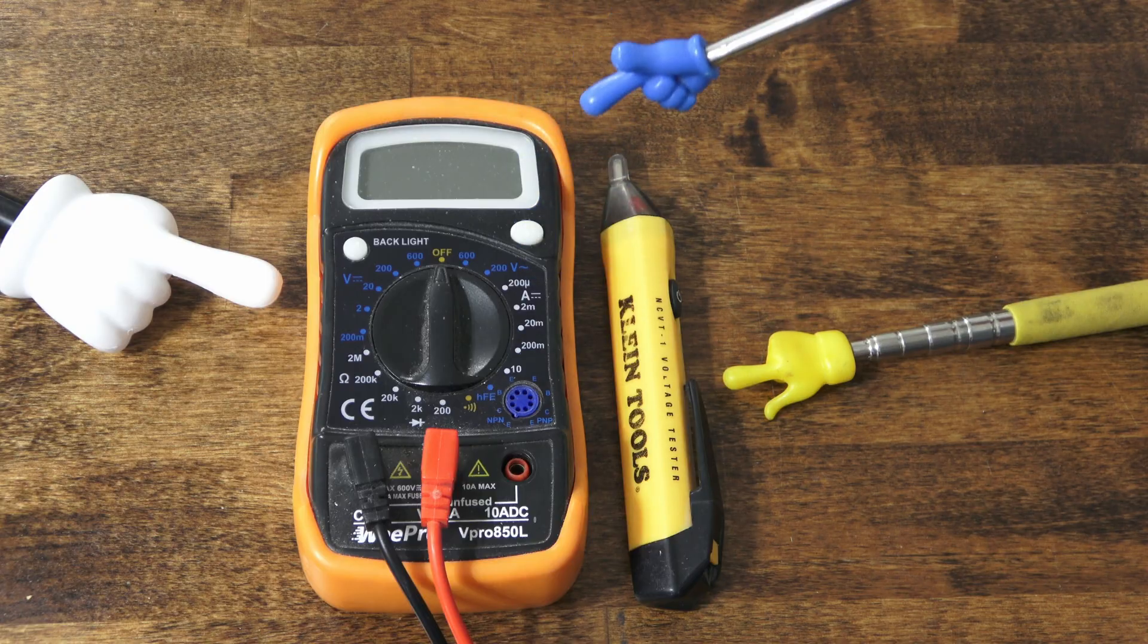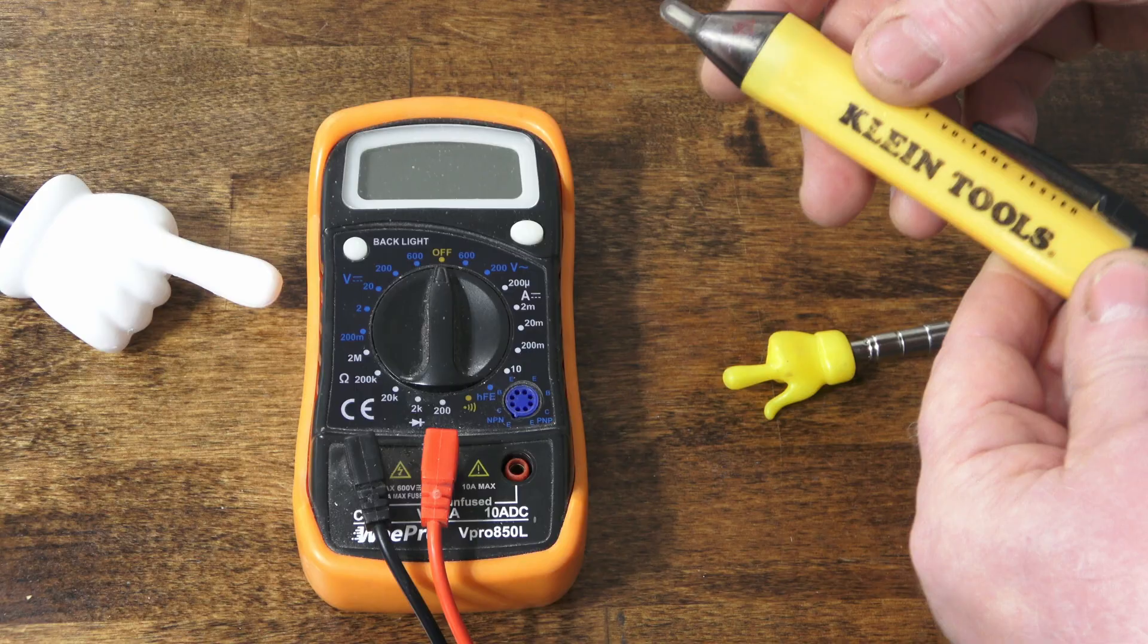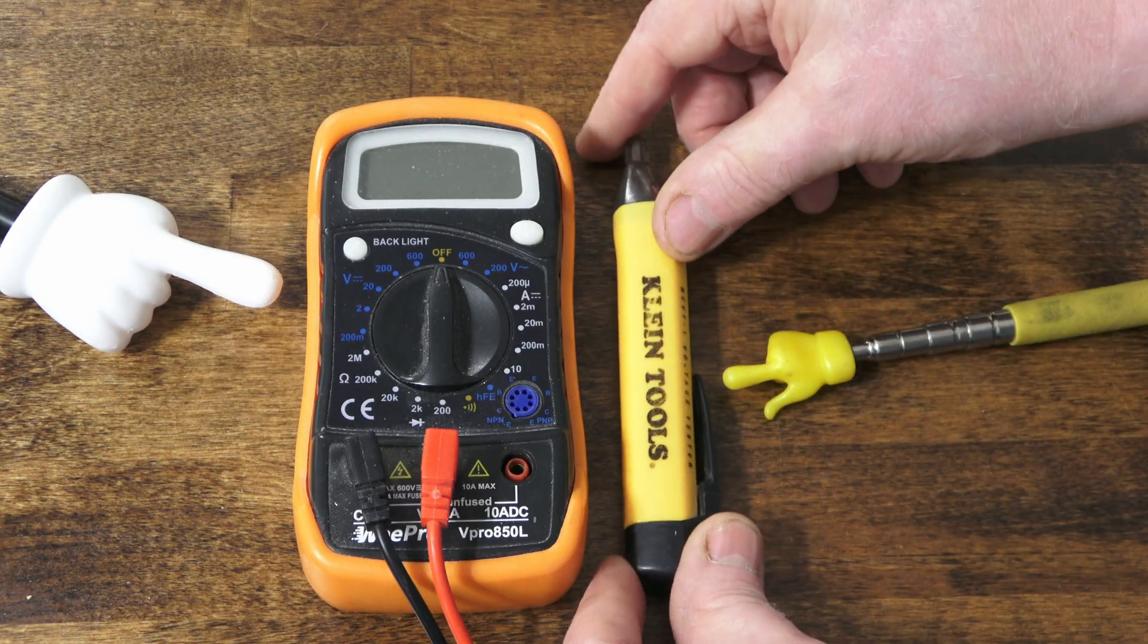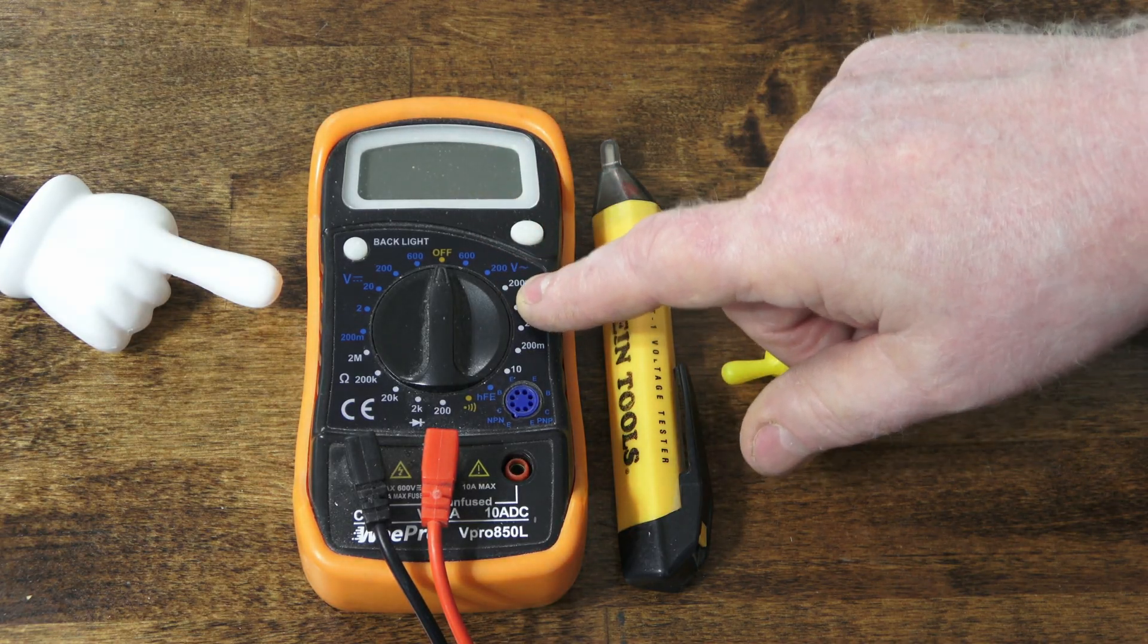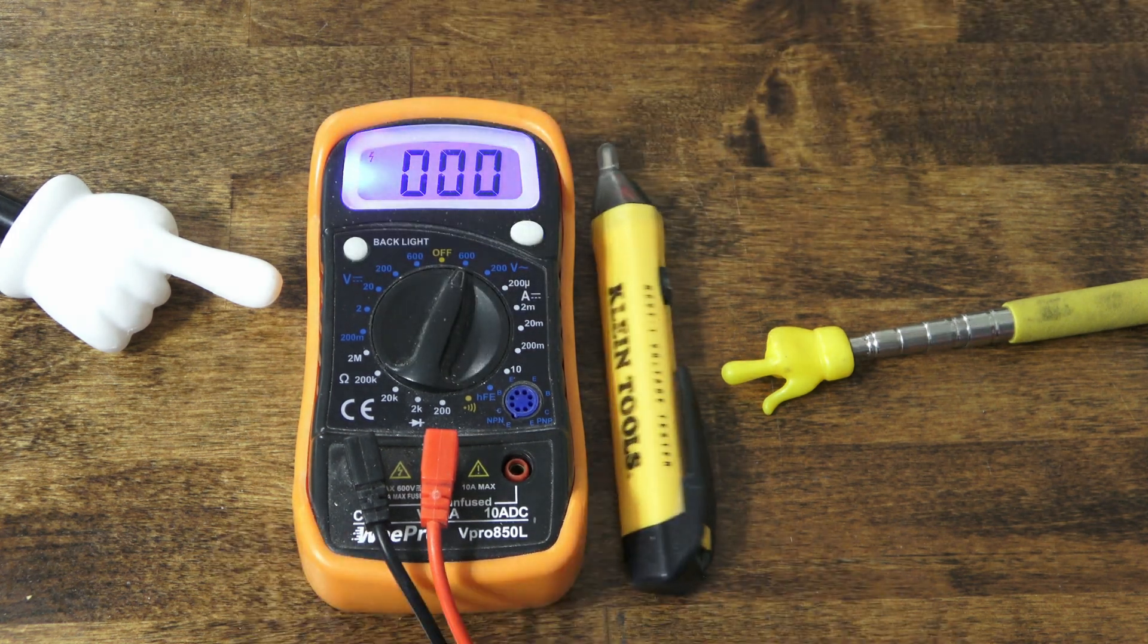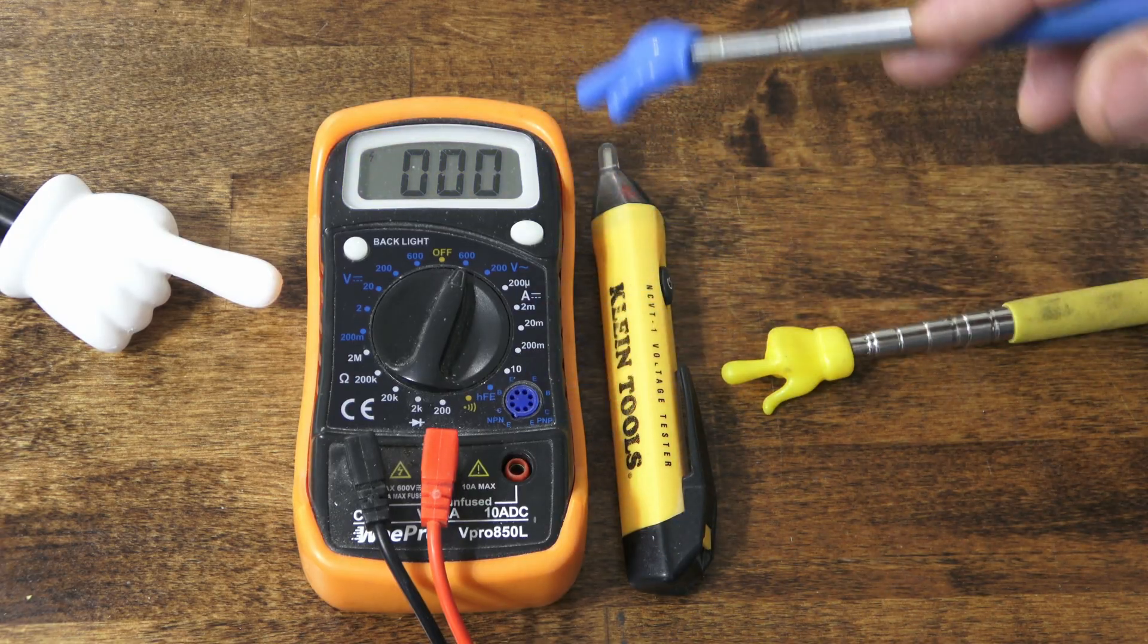Here I have a couple devices that you can use to check for presence of power. This one here is pretty cool. You don't have to break the wire. You can just touch the insulation of the wire and it will represent power or not. Then we got a meter. I'll be checking for 240 volts. So I'll choose 600 volts. Go to the AC side. I'll supply a link for these items in the description.